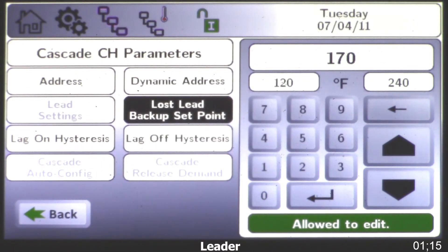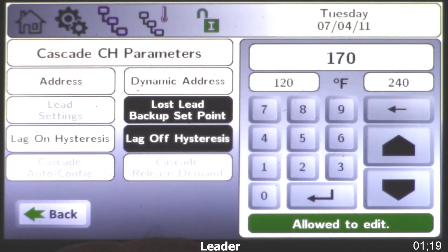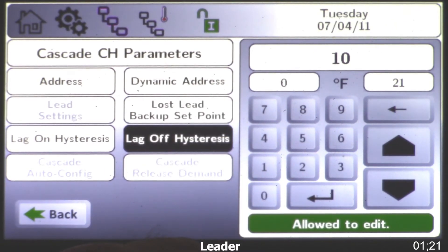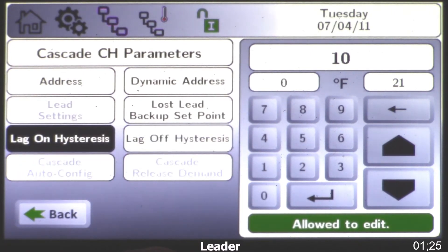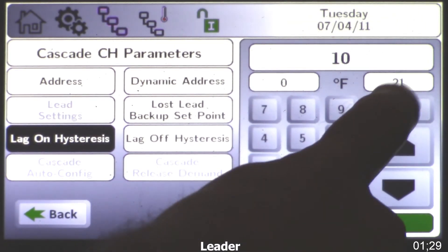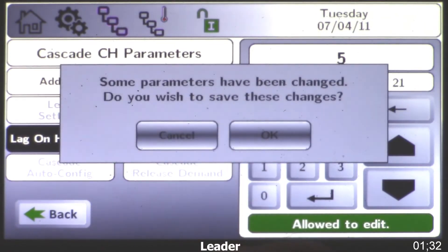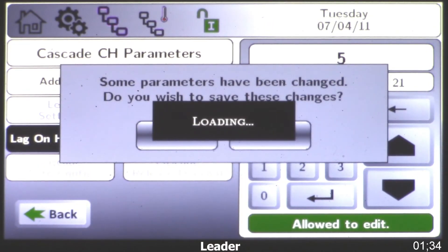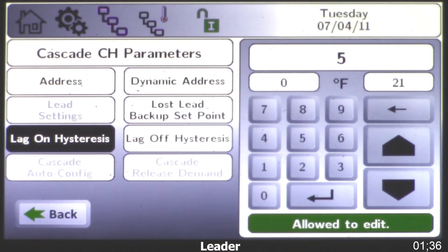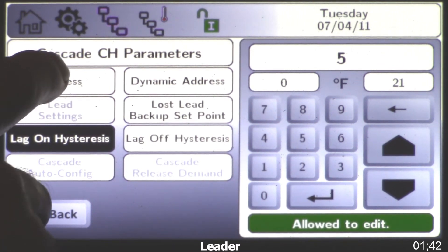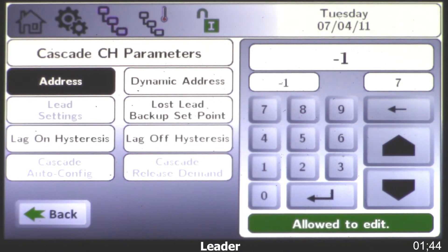Now you also have your on and off differentials, otherwise known as hysteresis. Here a 170 setpoint with a 10 degree off hysteresis will give us 180. The on differential or on hysteresis is also set for 10. If you want to adjust those, just back them out, choose your value, and click OK. In this example we now have a 180 off point and a 165 on point.